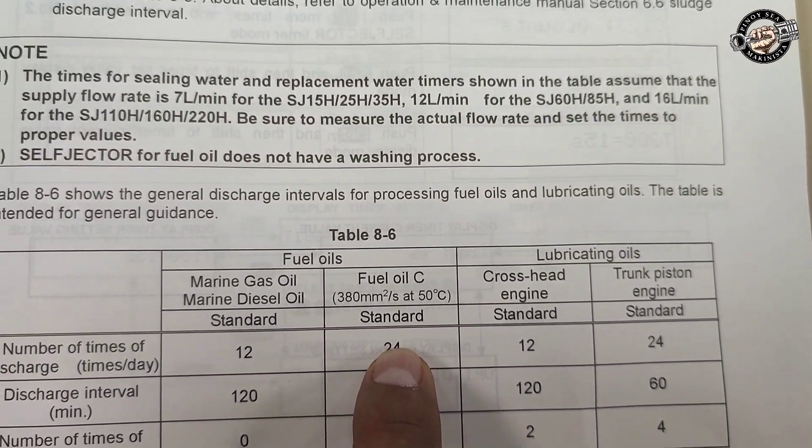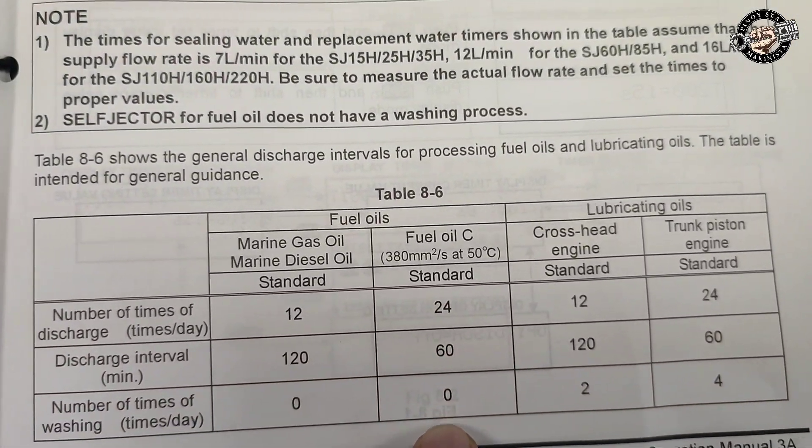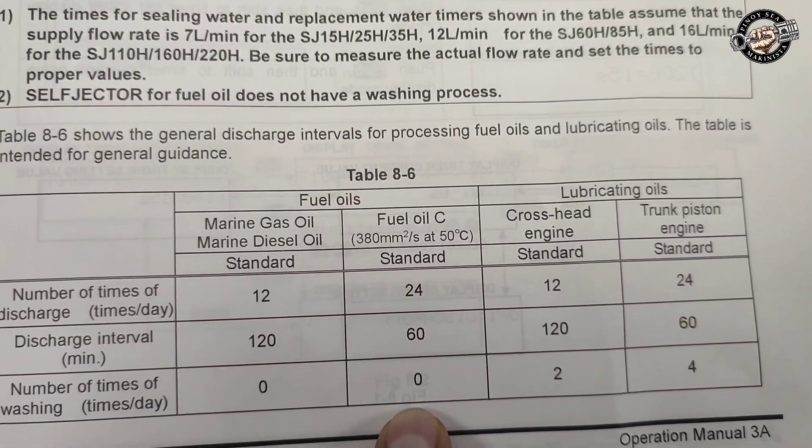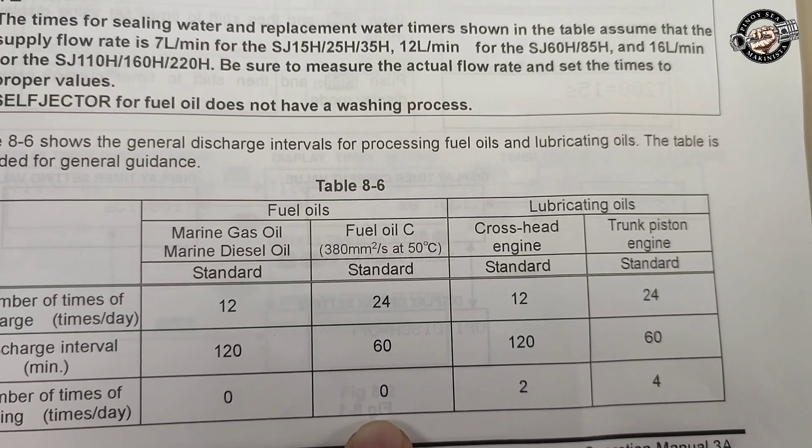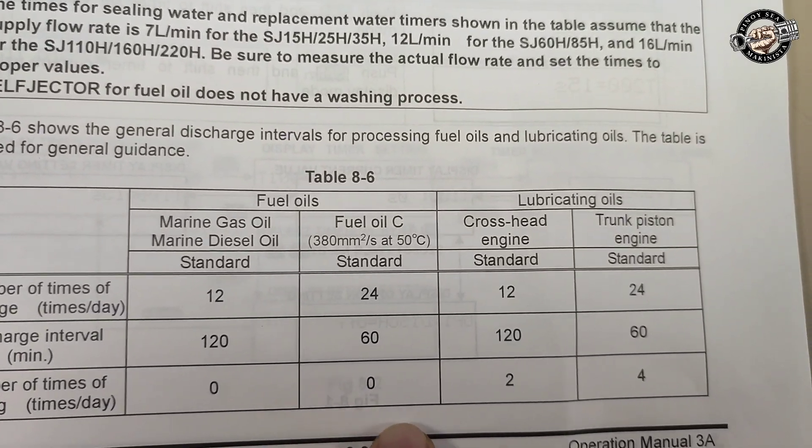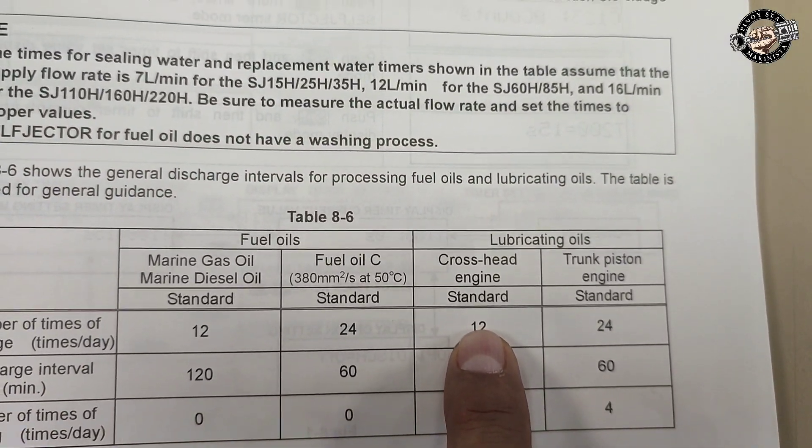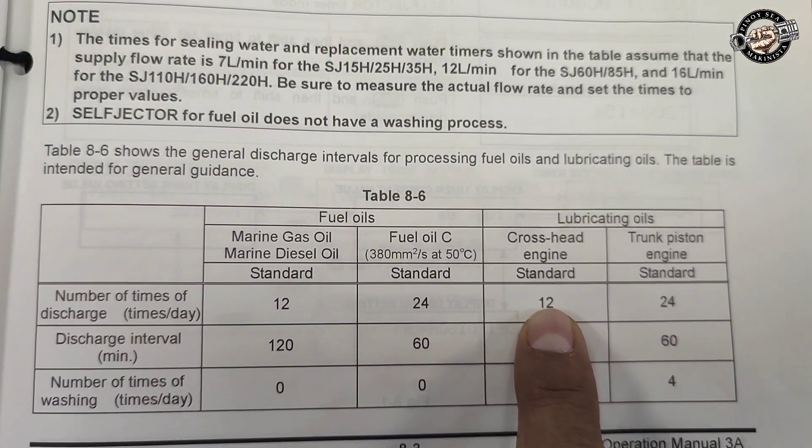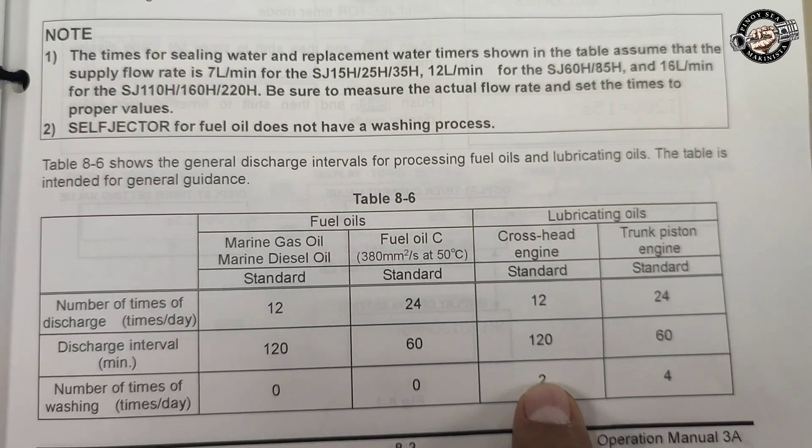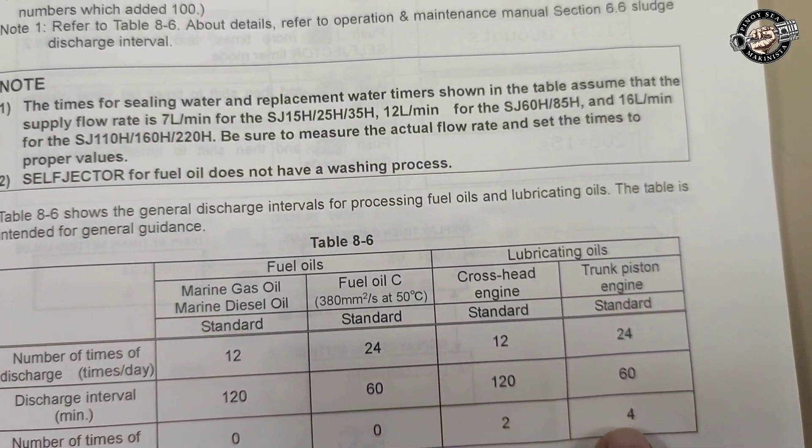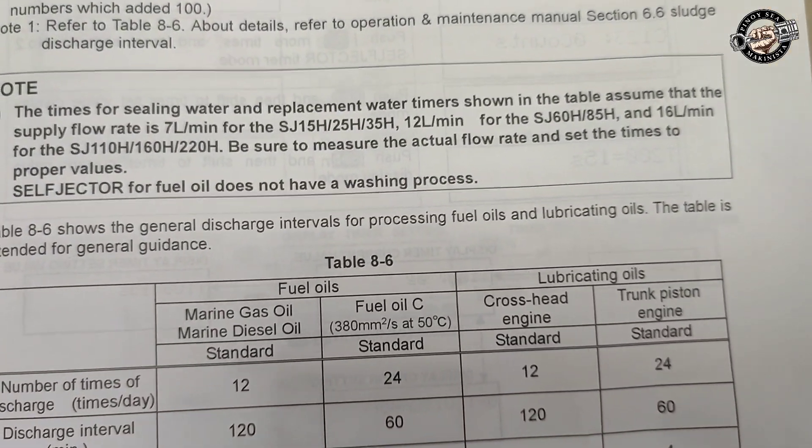For heavy fuel oil or low sulfur fuel oil, it is 24 times per day and the sludge discharge interval is 60 minutes or every hour. For your lubricating oils for engines like crosshead or trunk piston, it is 12 times per day.